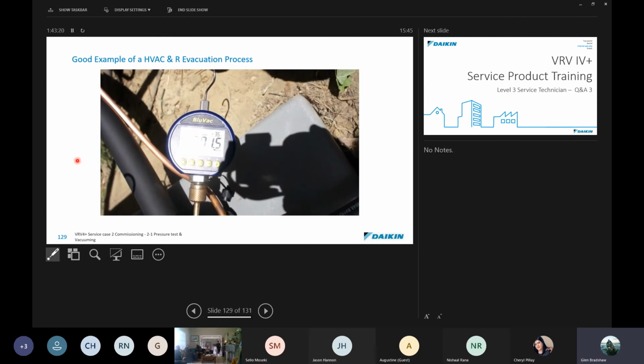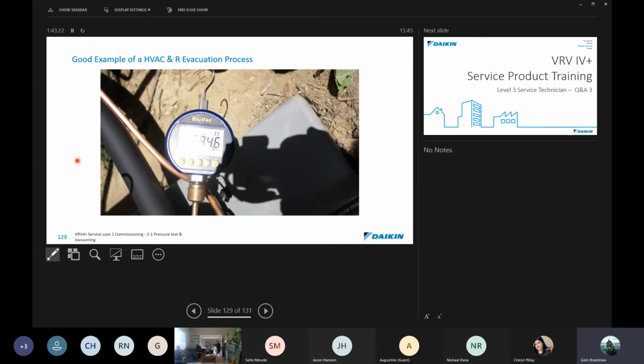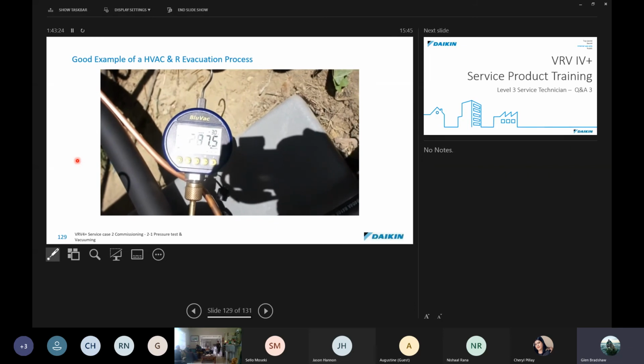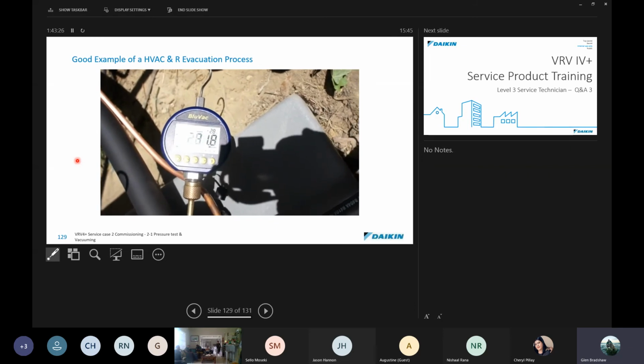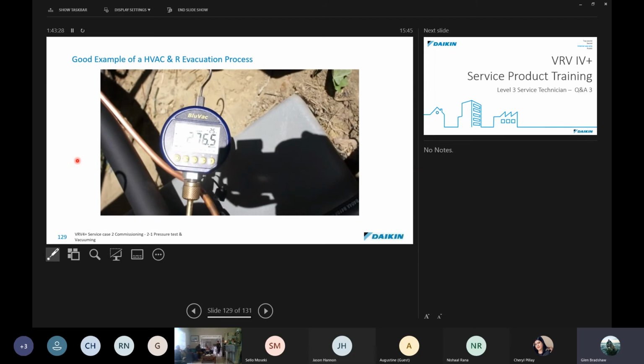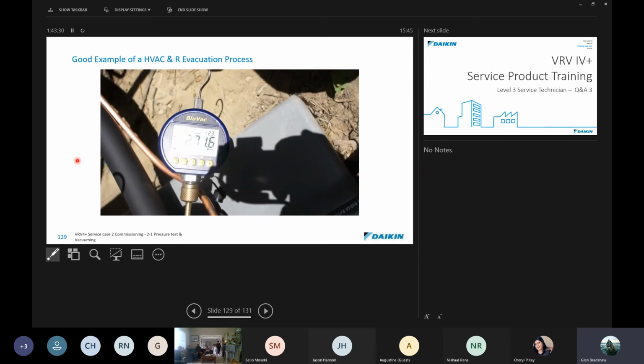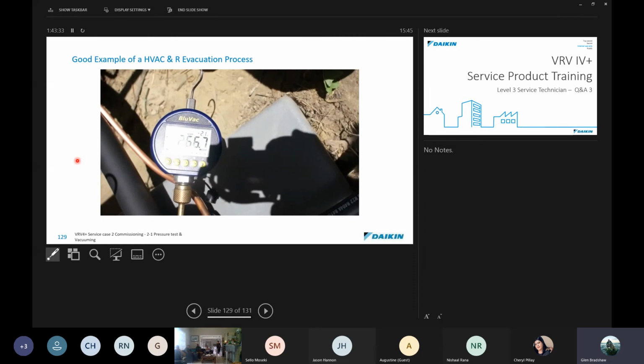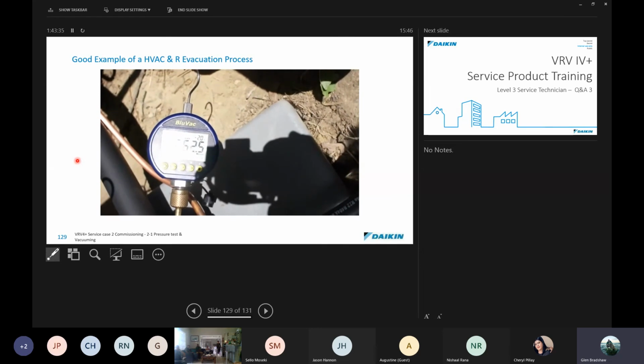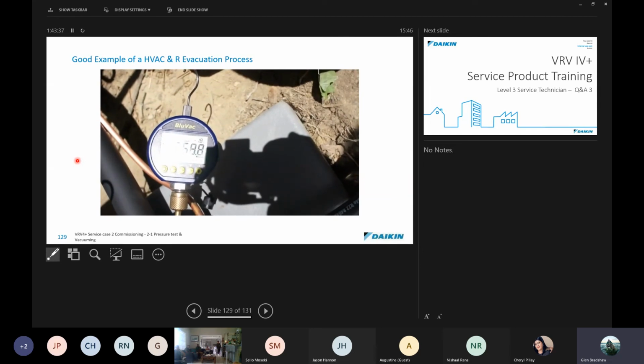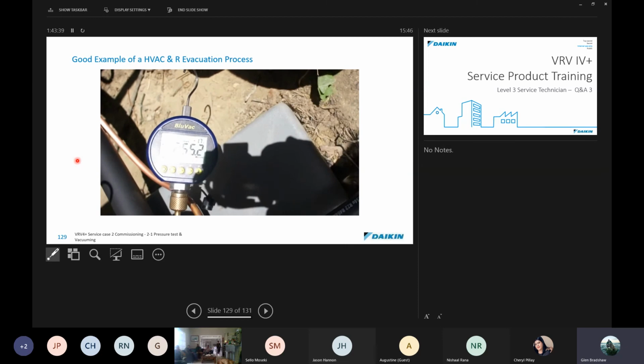But right now, it's been running for less than 5 minutes, less than 3 minutes probably, and we're at 200 microns with this pump. So we're going to let this run a few more minutes, then I'm going to isolate the core tools, and we'll see how stable our vacuum is, and where it levels off at. But you can see how quickly we can get down below 500 microns.